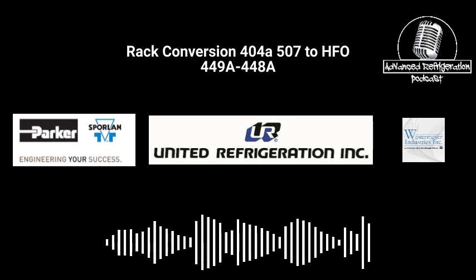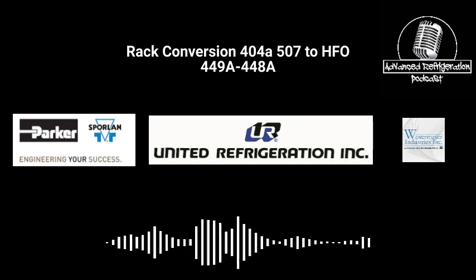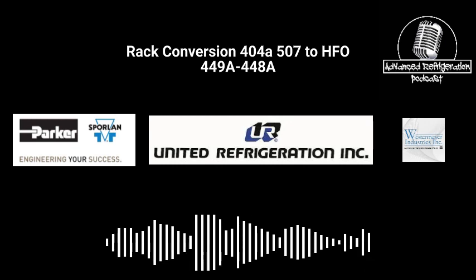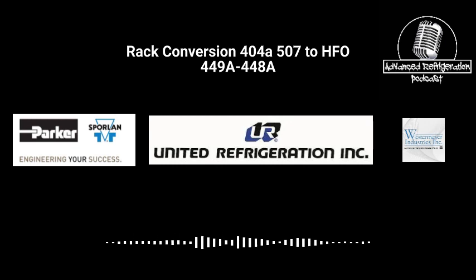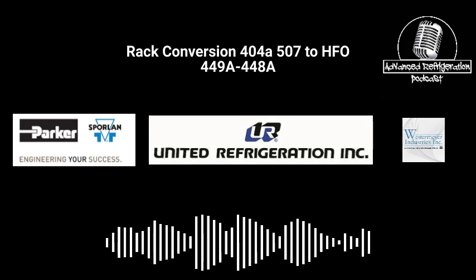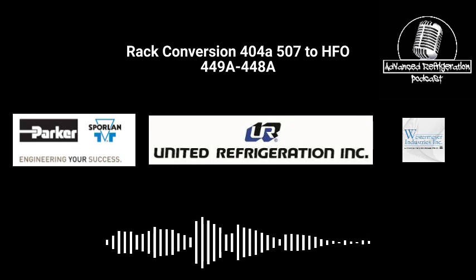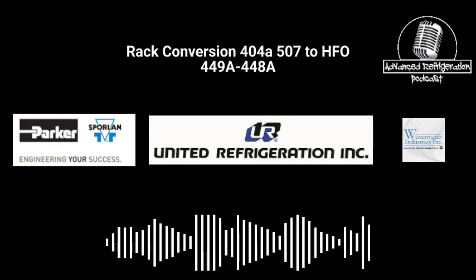Anything like that, guys, if you're trying to add on to these retrofits, if you're trying to upsell a digital compressor, it's going to make it go so much smoother. But regardless, that doesn't need to be done for the retrofit. Just do the gas changeover itself following what we laid out here: get the liquid injection put in, get ball valves that look like they're leaking or are going to leak changed out, solenoid valves that are leaking changed out. You don't have to change them, but if they're leaking, get them out of there and get them rebuilt. Then go through everything, and if you find hoses that are leaking, just get rid of them. I'm a big proponent, I'm no longer using the armored cap tubes, I switched over to reflex hoses.